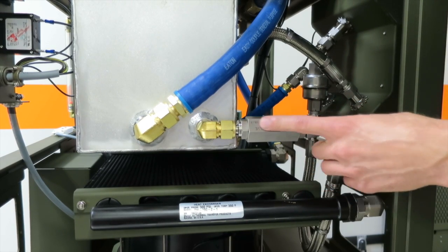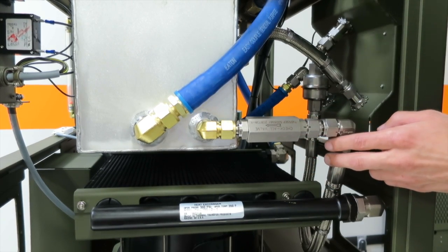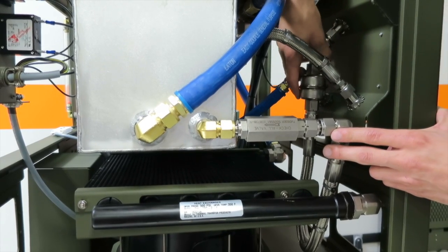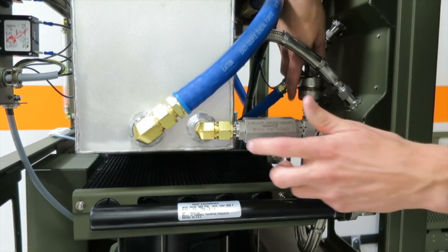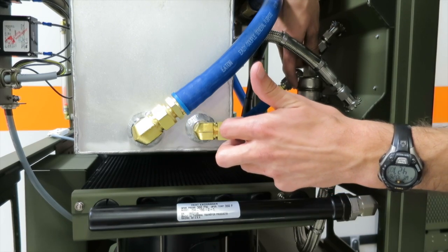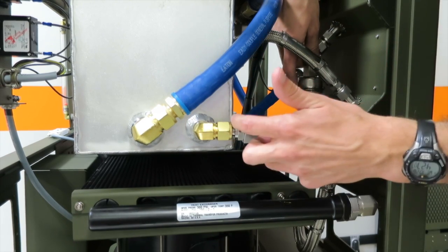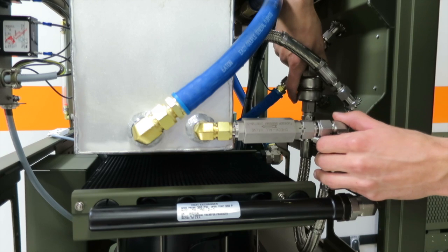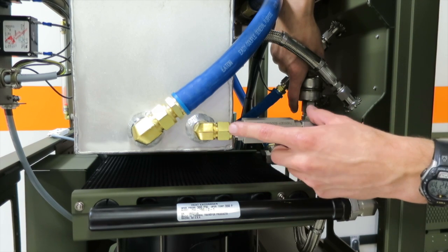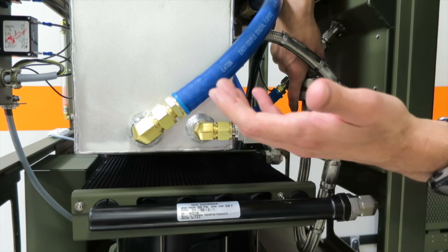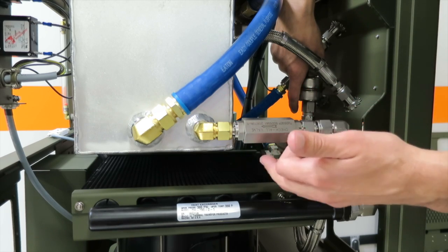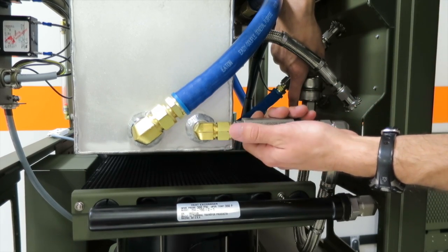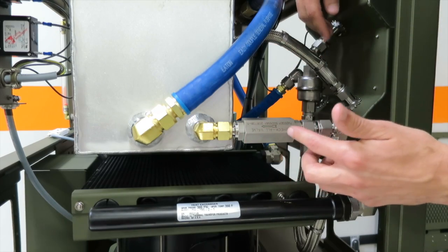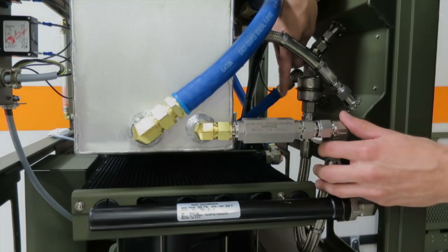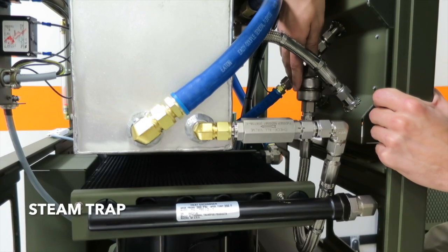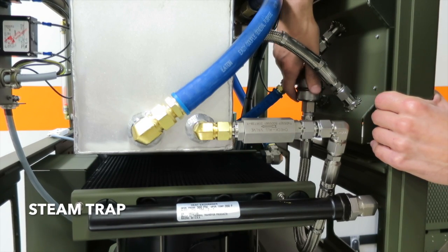So this check valve is very important because if, say, a vacuum is formed in the chamber, this prohibits water being sucked back into the chamber through this valve. Also, this is a backflow prevention during vacuum leak tests. This check valve seals off so there's no vacuum leaks back to the chamber. So the steam trap is very important to the sterilizer operation.